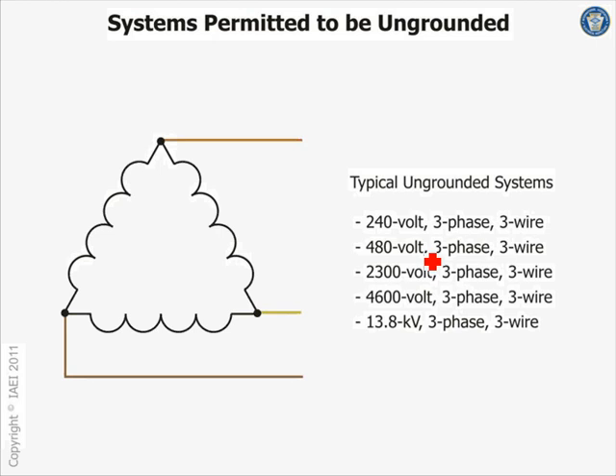Here you're running three-phase, you'd be running three-phase motors at 240 volts. Is there such a thing as a 208 system that's running 208 volt motors? Yes. So you don't need a neutral on that system. Yes. But it does not qualify, if you were to feed it into a building, you have to ground it.